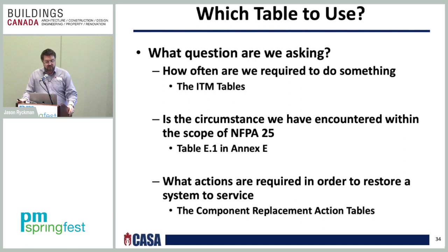Is the circumstance we have encountered within the scope of NFPA 25? Are we actually talking about NFPA 25 or another standard? You look in Table E.1 in Annex E for that information. And then what actions are required in order to restore a system back into service, which we just looked at, is the component replacement action table that you would look at.